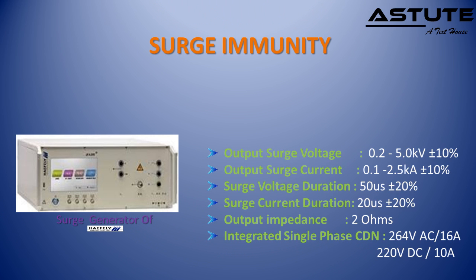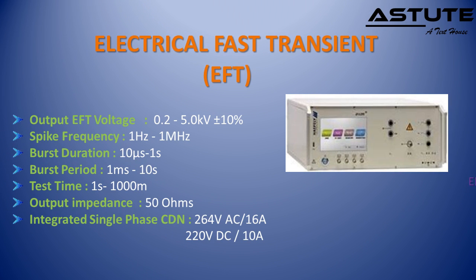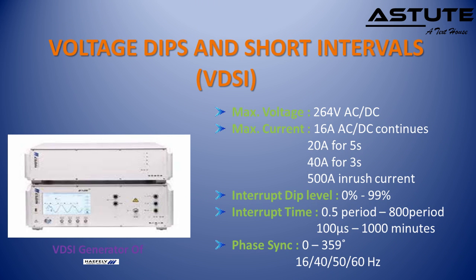For surge immunity testing of equipments, we use surge generator of Haefely with the output surge voltage up to 5 kV. For electrical fast transient immunity testing of equipments, we use EFT generator of Haefely with output EFT voltage up to 5 kV. For voltage dips and short interruptions immunity testing of equipments, we use VDSI generator of Haefely with interrupt dip levels up to 99% of voltage.